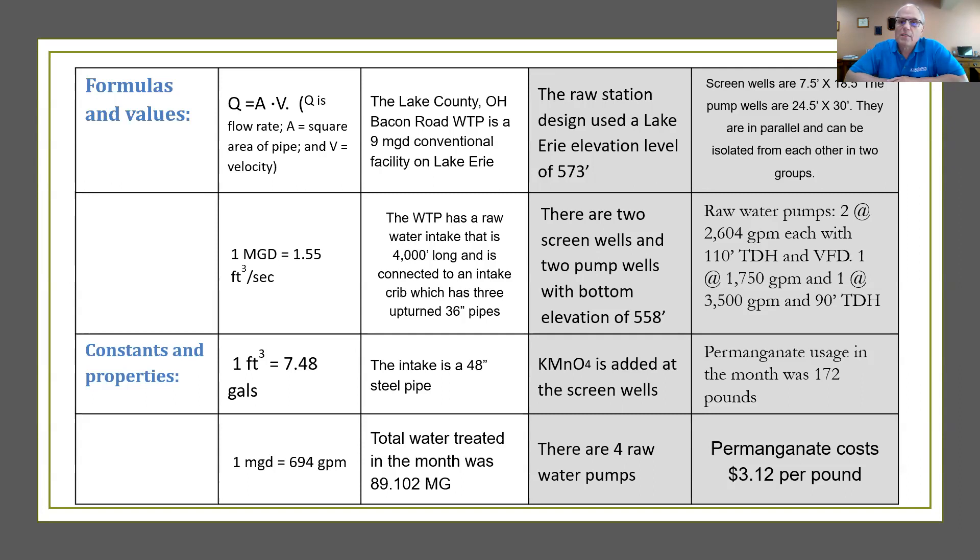Just like Aquarius, the Bacon Road plant adds potassium permanganate at the screen wells. There are four raw water pumps. We have the dimensions of the screen wells there you can see. Move my hand out of the way here. Screen wells are seven and a half by 18 and a half. The pump wells are 24 and a half by 30. They're in parallel and can be isolated from one another into two groups.